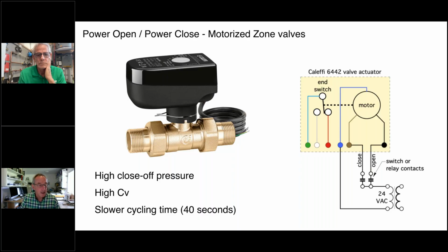Very high close-off pressure, because instead of a spring closing that paddle, you've actually got a motor being driven electrically to close that ball. And ball valves are going to have a higher CV rating, meaning less pressure drop through that valve. And it is a slower cycling time, 40 seconds. So that would minimize any potential for water hammering effects in the system. So that is an option. It's probably not as common as the paddle valve in residential applications, but these are excellent valves in other applications where you need these features.